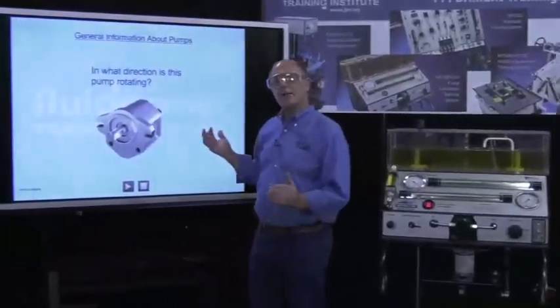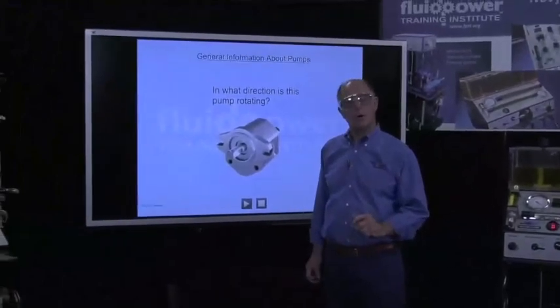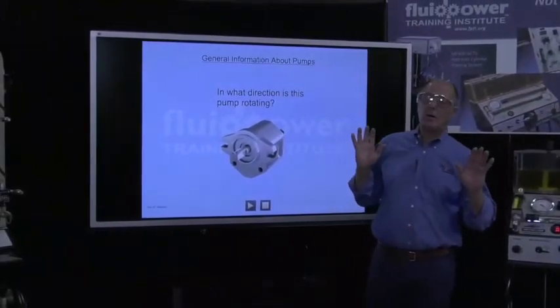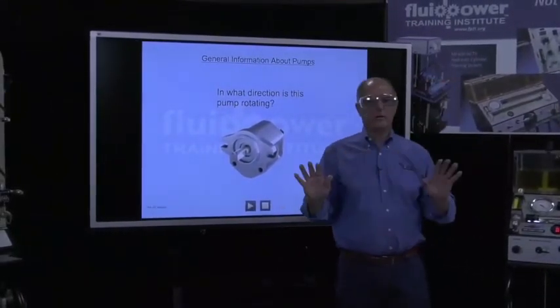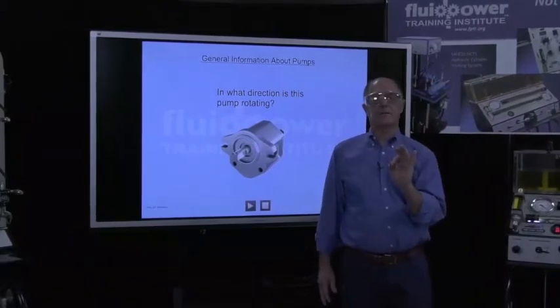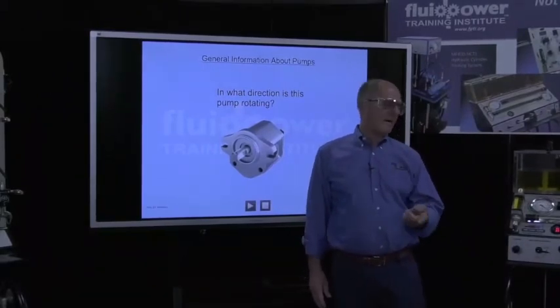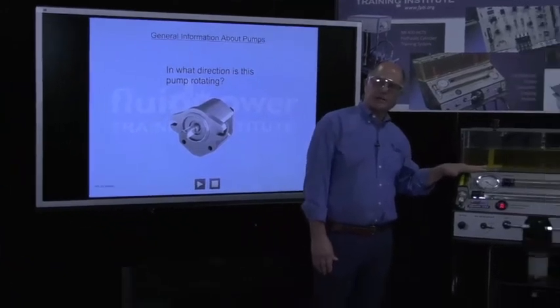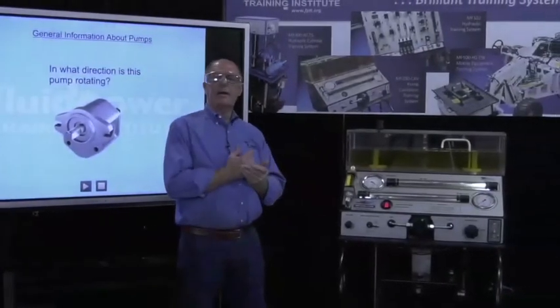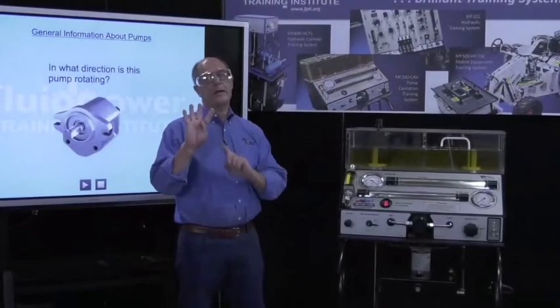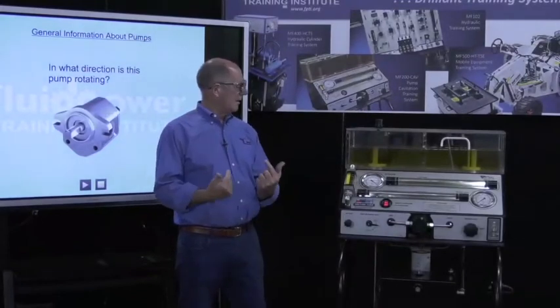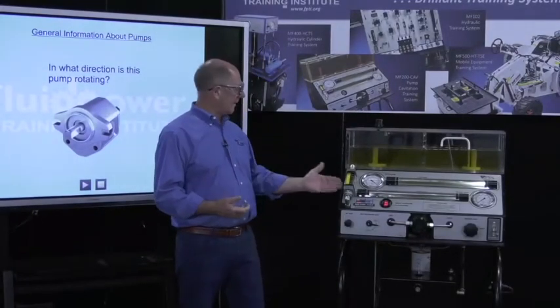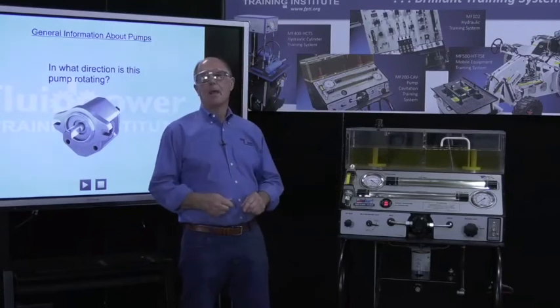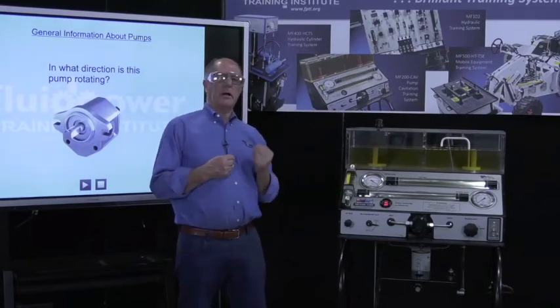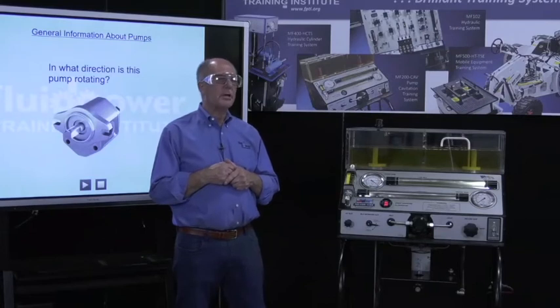What we first and foremost started out with is we showed you how the intake side of a hydraulic pump works. And we said it's absolutely critical that I get to know what the point of reference is. With that point of reference, we went and started up this simulator and we demonstrated 4 things. 1, we got to know the patient, meaning we got to know what the point of reference is, the flow rates, the pressures, etc. Then we said, let's start out by looking at cavitation.